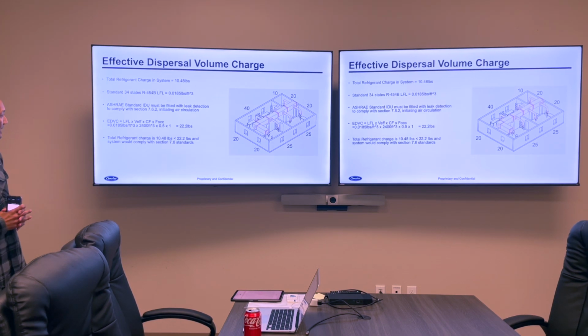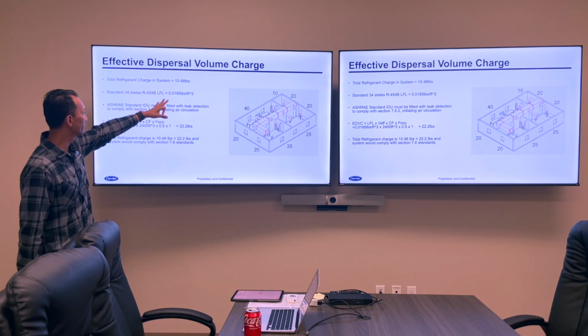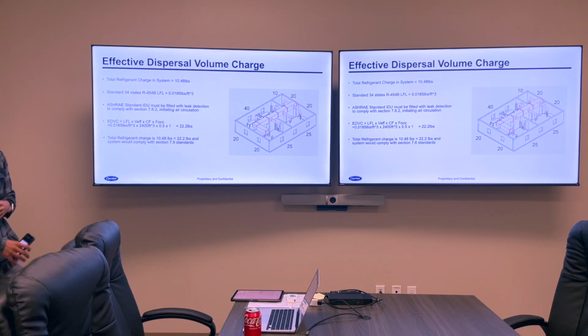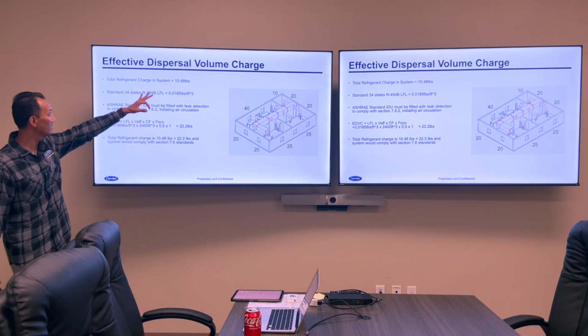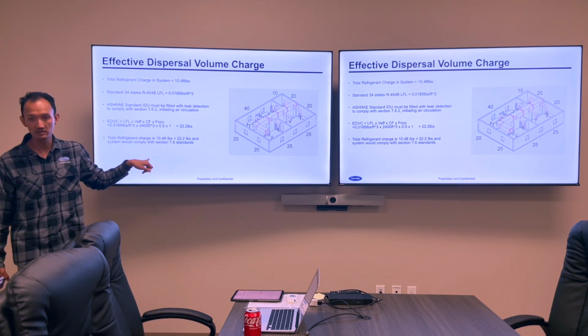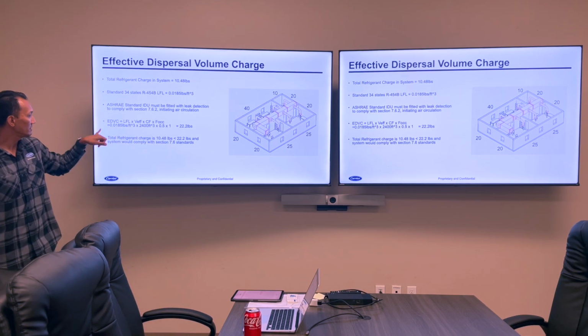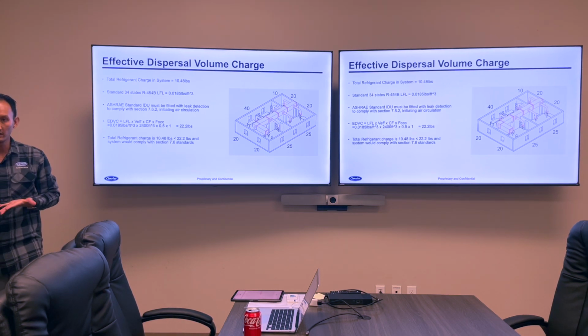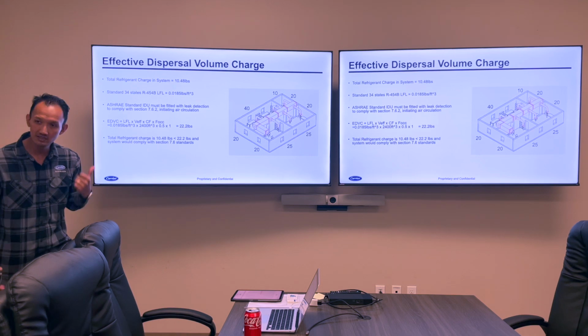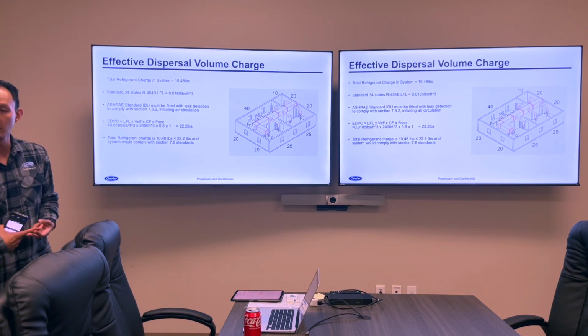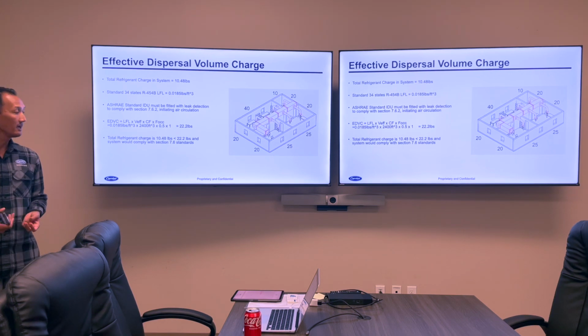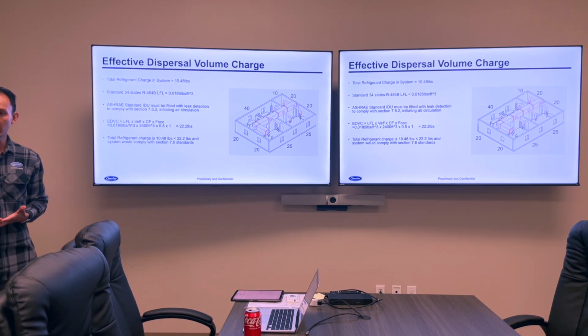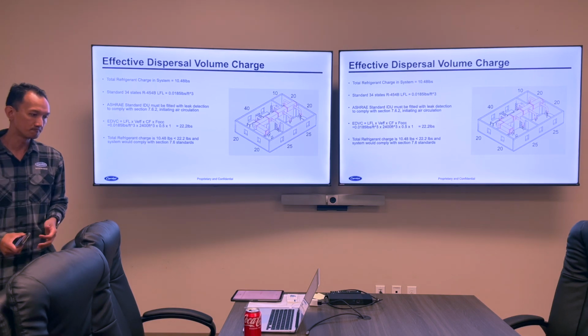So if we go ahead and look at our space, we have a total refrigerant charge of just under 10.5 pounds. We have the LFL of R454B. And if we plug in all of those numbers, we get 22.2 pounds for the space. Since 10.48, which is our total refrigerant charge, is less than 22 pounds, based off of the EDVC calculation, this system would comply with ASHRAE section 7.6. So we didn't need an SV box. This is just a VRF system with a one-to-one system, and it passes. We don't need any extra provisions for an SV box or anything like that.